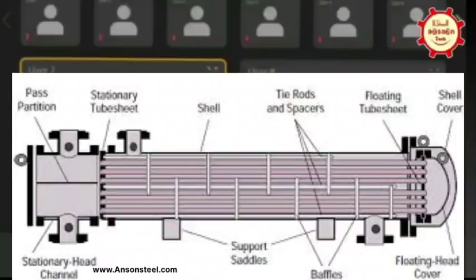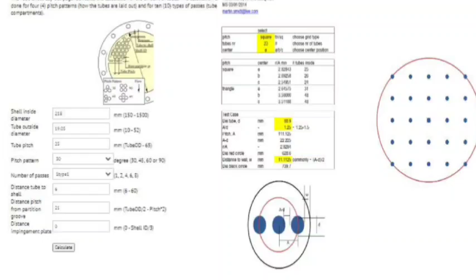D1C is tube shell side pressure high and tube side pressure 0 or minimum - not full vacuum. And D2C is tube side pressure high and shell side pressure 0 or full vacuum, that is 16. And D3C is both actual design pressure maximum - 16, 0 and 0, 16. This is the case right now.